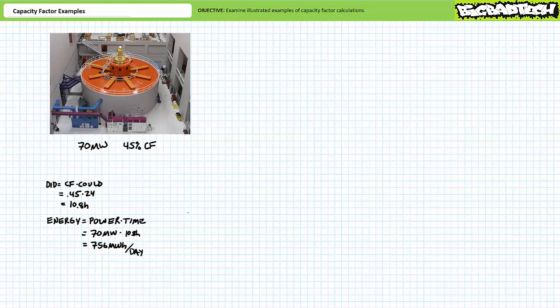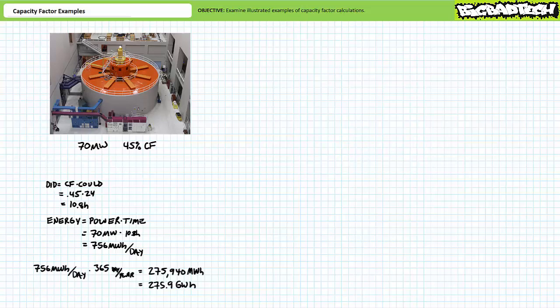Energy is power times time. 70 megawatts times 10.8 hours is a daily energy production figure of 756 megawatt hours. If this turbine did this for 365 days in a row, it would ultimately produce 756 times 365, or 275,940 megawatt hours — roughly 275.9 gigawatt hours — in the course of a single year.